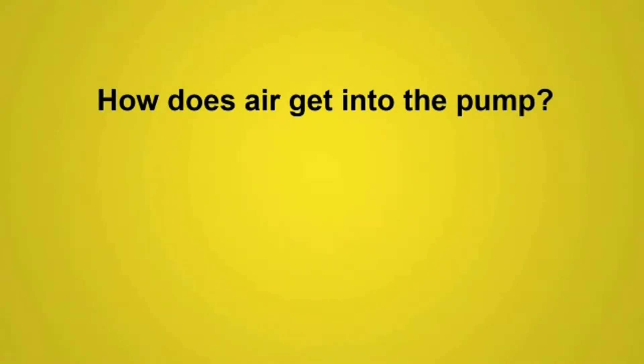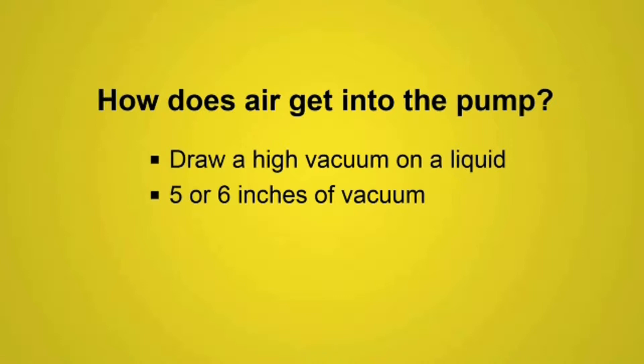How does air get into the pump? On a single-pipe system, one way is to draw a high vacuum on a liquid, five or six inches of vacuum would be considered enough. This outgasses the oil.